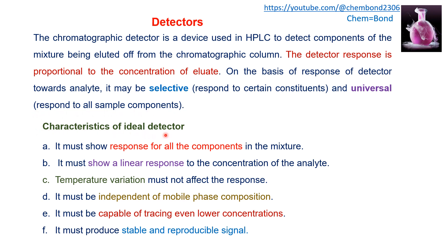There are some characteristics of an ideal HPLC detector. It must show a response for all components in a mixture. It must show a linear response to the concentration of the analyte. Temperature variation must not affect the response. It must be independent of the mobile phase composition, especially in gradient elution where the mobile phase composition is changing. It must be capable of detecting even lower concentrations, and it must produce a stable and reproducible signal.